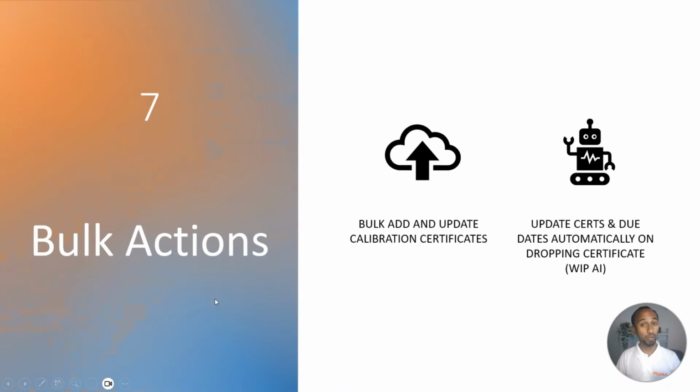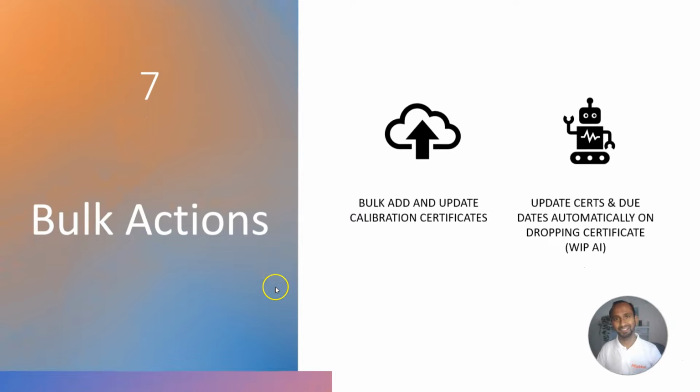Number 7. Bulk actions. You can add and update a number of calibration certificates that you have in a single shot. There is an upcoming artificial intelligence system that will detect your certificate and update the specific instrument on the system and reduce your work going forward.